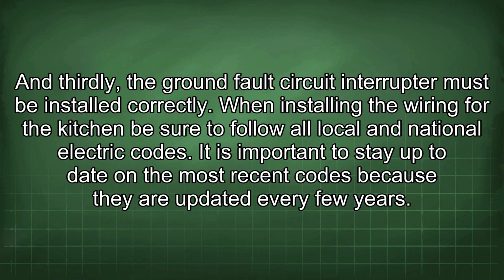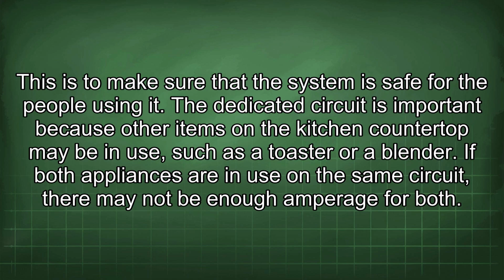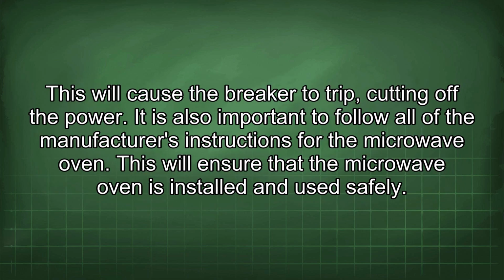When installing the wiring for the kitchen, be sure to follow all local and national electric codes. It is important to stay up to date on the most recent codes because they are updated every few years. This is to make sure that the system is safe for the people using it. The dedicated circuit is important because other items on the kitchen countertop may be in use, such as a toaster or blender. If both appliances are in use on the same circuit, there may not be enough amperage for both. This will cause the breaker to trip, cutting off the power. It is also important to follow all of the manufacturer's instructions for the microwave oven. This will ensure that the microwave oven is installed and used safely.